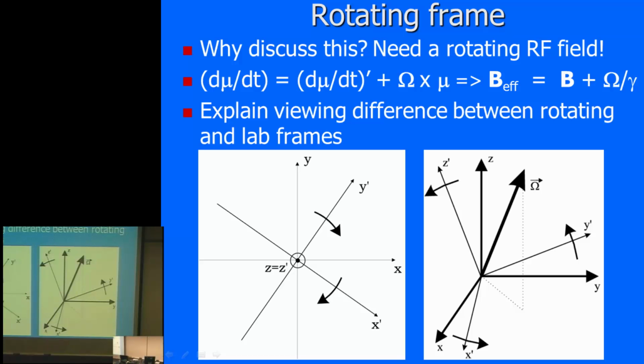Okay, but there is actually a reason behind this rotation, and that is from the Larmor equation. It is from that precession, because naturally, if I have a main field pointing this way, say just 1 Tesla, and I have a spin, a proton, it precesses around this main field. What is the frequency at which it will precess around this main field? Well, the answer is the gyromagnetic ratio. So if I have a 1 Tesla main field, the Larmor frequency, meaning the rate of precession, is in fact 42 megahertz.